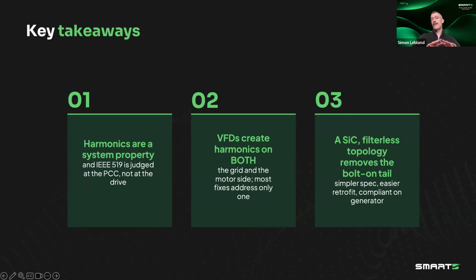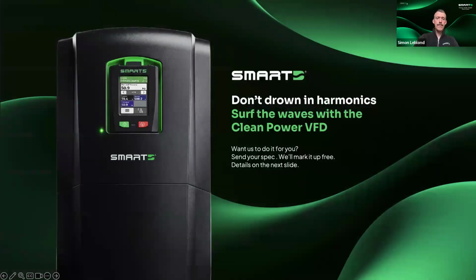And finally, the silicon carbide based filterless topology that we've developed removes any kind of bolt-on mitigation solution. So it gives you a simpler spec, easy retrofit, and compliance that holds up in a generator and UPS situation as well. So that's it for me. I'd say don't drown in harmonics. You can surf the wave with our Clean Power VFD.